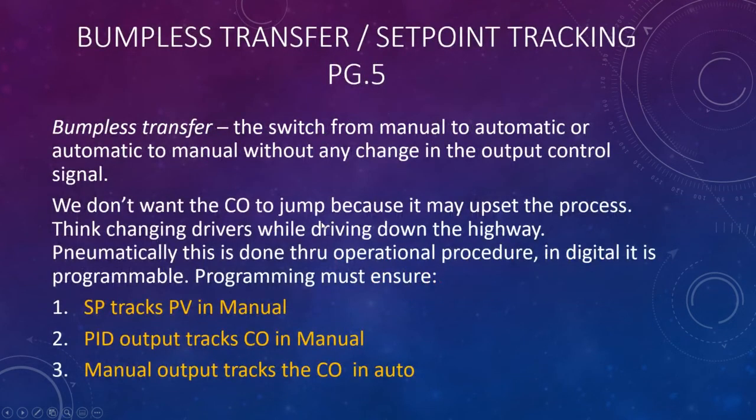Okay, another unique thing that we have to consider when we're dealing with different controllers, specifically pneumatic ones. Well, I guess it works pneumatically and digitally. And this is something that we call bumpless transfer. Bumpless transfer is something that we want to do, and set point tracking is something that allows us to do it. Let's look at the definition here: switching manual to automatic or automatic to manual without any change in the output control signal.